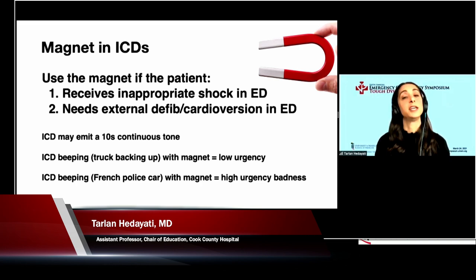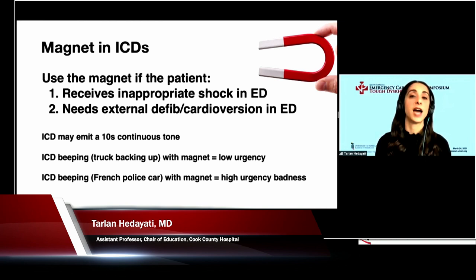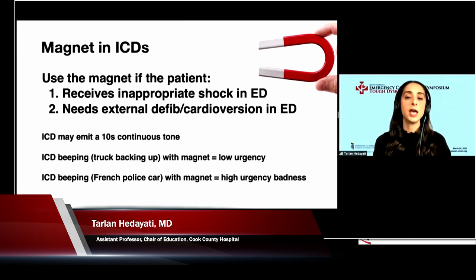The device may make some sounds when you put the magnet on, and that's an indicator to you—it's audible, you'll hear it, telling you a magnet has been placed and that it's about to go offline. When you put the magnet on, it emits a 10-second tone.